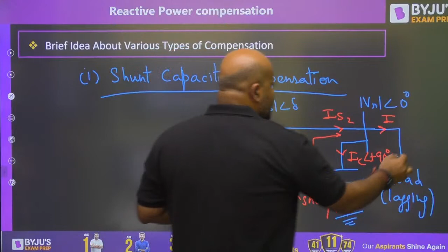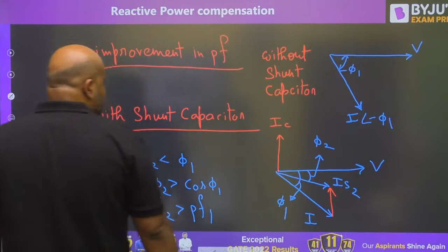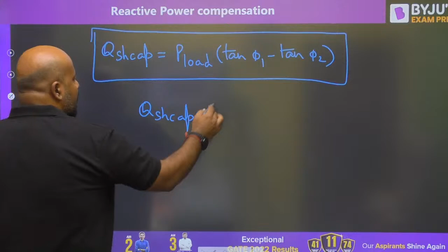You know what is phi 1, you know what is phi 2, you know what is P load. This is P load. Is it clear everybody? One more equation you can write for the reactive power supplied by the shunt capacitor. If it is a 3-phase, you can write 3 times V phase square upon XC per phase. Now what is XC per phase? XC per phase is the shunt capacitor you are providing per phase. So that XC per phase you can write as 1 upon 2 pi F capacitance per phase. So if you put it here, Q shunt capacitor is equal to 3 times V phase square times 2 pi F capacitance per phase. So one more important equation that you can follow.